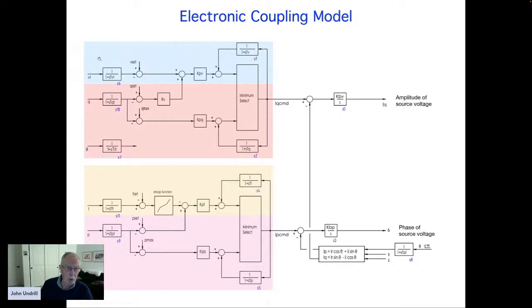blue and pink, controls voltage according to a drooping relationship between voltage and reactive power. And this controller compares frequency with frequency set point and controls real power according to a drooping relationship between a set point for either speed or power and actual power output over here. I'm shadowing the drooping relationship as I speak. The voltage controlling part of the system wants to control that component of current that accounts for reactive power, and the real power, the frequency controller, wants to control that component of current that relates to real power.